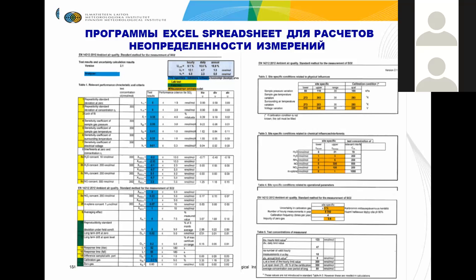So, and we have trained the local operators how to use this uncertainty calculation method, so that part of the parameters for these uncertainty measurements are of course coming from the National Reference Laboratory, because that is part of the uncertainty of all of the measurements, but some of the parameters have to be defined in the network operator, and also in the station itself, and also at the end in each of the single instrumentation that is used for the measurement, and of course the field calibrator and the gas bottles and everything. So it's quite a complex system to be able to calculate the total uncertainty of any measurement.